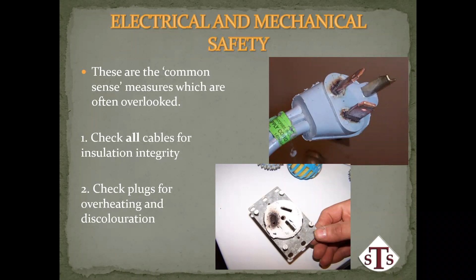So I've just pulled them out just in case you don't read the manuals to the end, which a lot of people don't. There is an electrical presence, so inflammable gases may produce a risk. How you clean your transducer, and hopefully you do clean your transducer, has to be cleaned with very special chemicals. And I put there in brackets, no alcohol. That's not for the sonographer. That came about because of COVID. And we were told by the people whose machines we use in our training courses that you cannot use hand sanitizer to clean the transducer. It sounded just so simple and so obvious. But the 70-75% alcohol in hand sanitizers actually seriously damages the transducer over time. So alternate cleaning needs to be used.